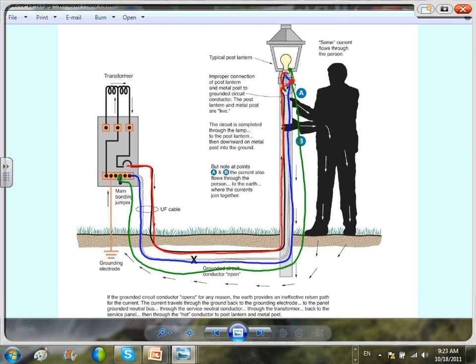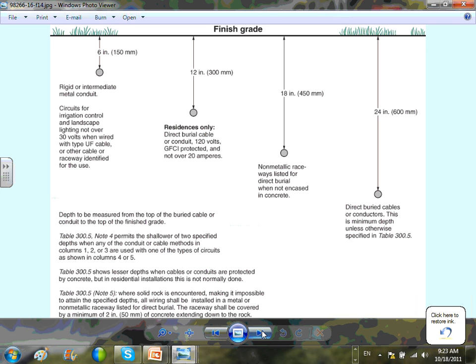What do you need to know? You need to know every time you send a circuit anywhere, you always send at least three conductors: hot, neutral, and ground. You do not want to depend on the ground to be your equipment grounding conductor because the impedance is too high. Okay, we got that one.